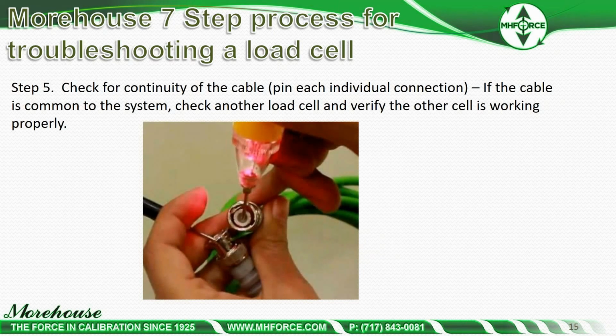Step 5, check for continuity. This is where we're verifying the pinouts. Check for continuity on the cable, pin each individual connection. If the cable is common to the system, check another load cell and verify the other load cell is working properly. So we check continuity. If we still don't see the issue and we have another load cell in the system, we can plug in the other load cell and verify that the cable's good. If the other load cell works well, now we can eliminate the cable. If the other load cell does not work well, then it points us back to the cable.